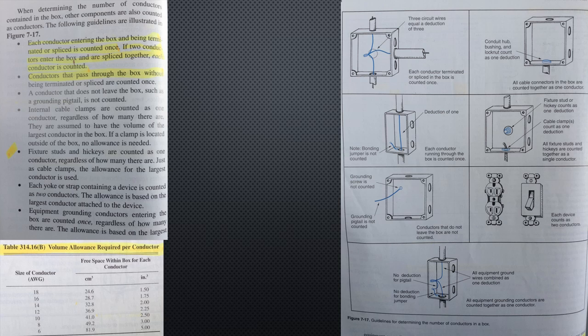Each conductor entering the box and being terminated or spliced is counted once. If two conductors enter the box and are spliced together, each conductor is counted. Conductors that pass through the box without being terminated or spliced are counted once. A conductor that does not leave the box, such as a grounding pigtail, is not counted.